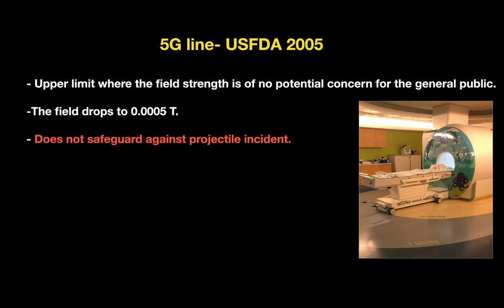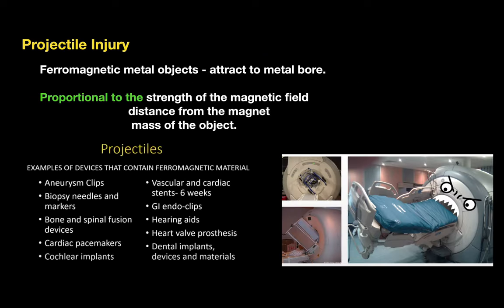There is a concept called the 5-Gauss line, given by the US FDA in 2005. This line is the upper limit where the field strength is of no potential concern for the general public, but it does not safeguard against projectile incidents. This line represents a field drop of about 0.0005 tesla.